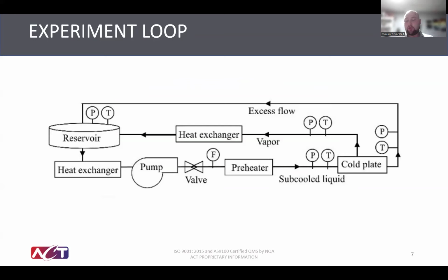Starting down here in the bottom right at the cold plate, you'll see there are 2 outlets as I've described: a liquid outlet and a vapor outlet. Both have pressure and temperature sensors on them, so we can measure those at both outlets to analyze how those are working. The liquid outlet very simply goes around, comes through, and drops into a reservoir, which is just a big storage tank for us so that we can run this very continuously. We don't have to worry about too little refrigerant in the lines.